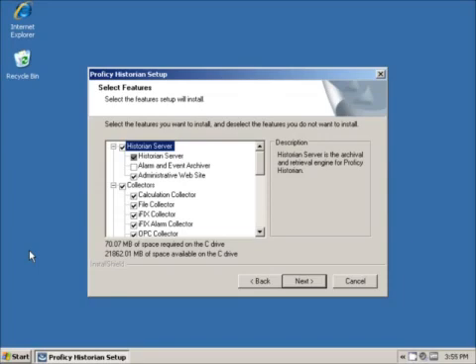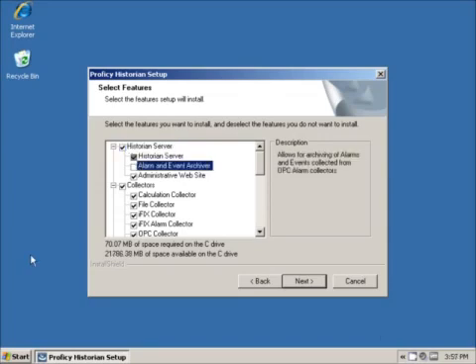The Historian server is automatically selected. The administrative website is only selected and available if you have a web server like IIS installed on the server already. I will add the Alarm and Event Archiver to the installation to permit logging alarms and events to the Historian server. The Alarm and Event Archiver is a licensed option and is included in the Enterprise license.